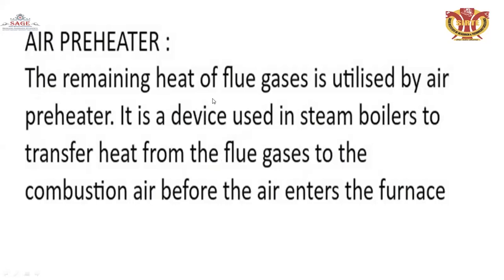The air preheater is another main component of the steam power station. The remaining heat of the flue gases is utilized by the air preheater. It is a device used in steam boilers to transfer heat from the flue gases to the combustion air before the air enters the furnace. When hot air is supplied in the combustion chamber, there will be a saving of fuel because combustion already begins with the mixing of fuel and hot air.